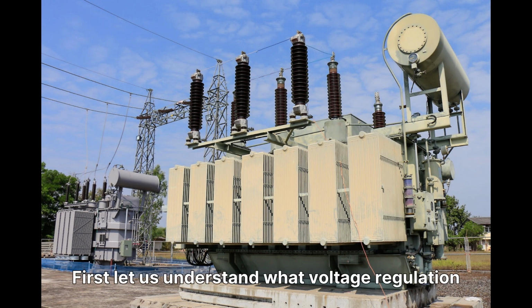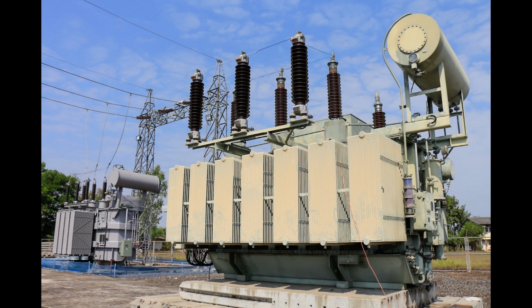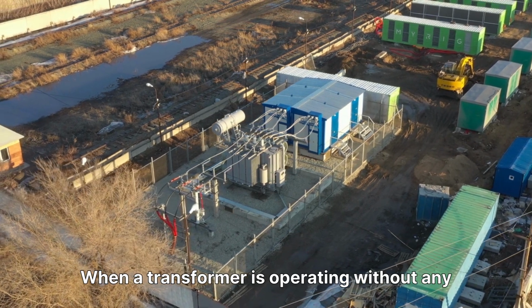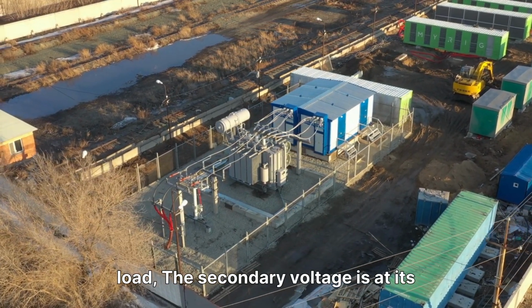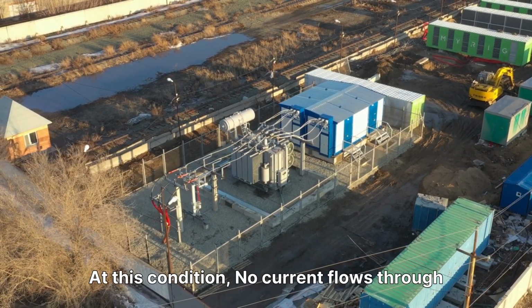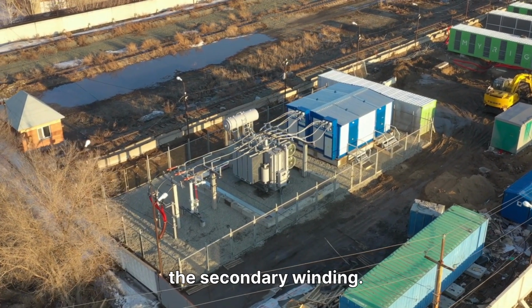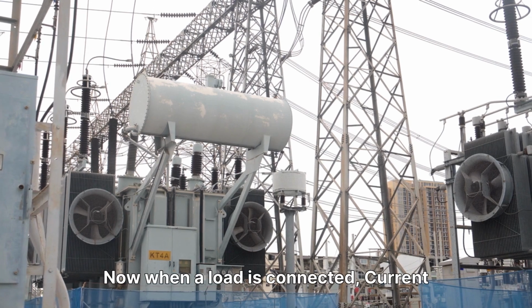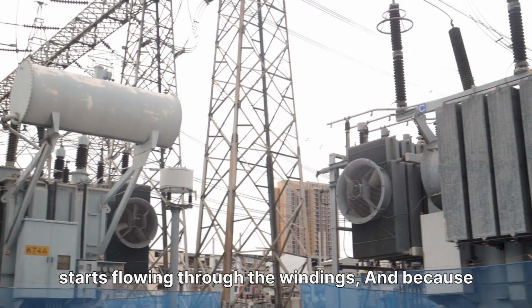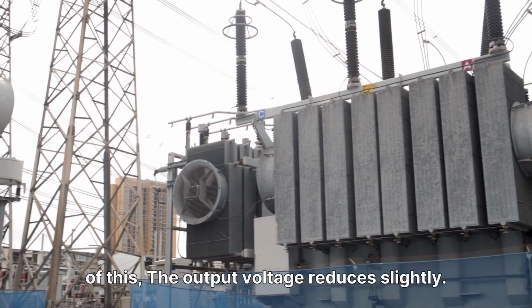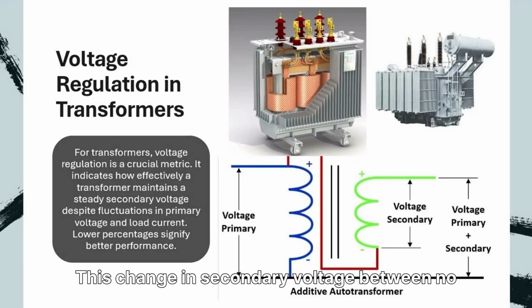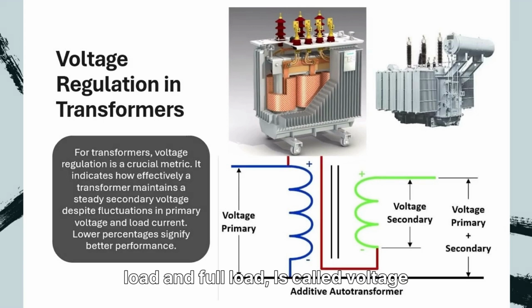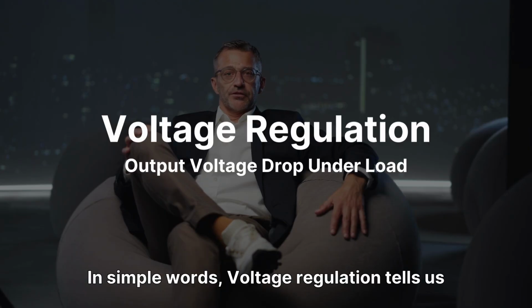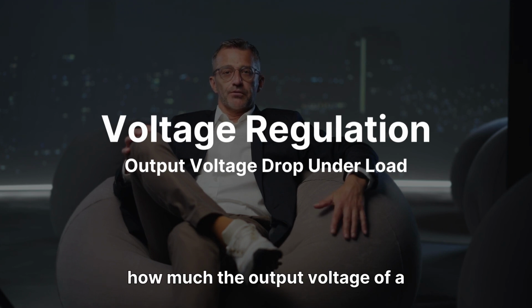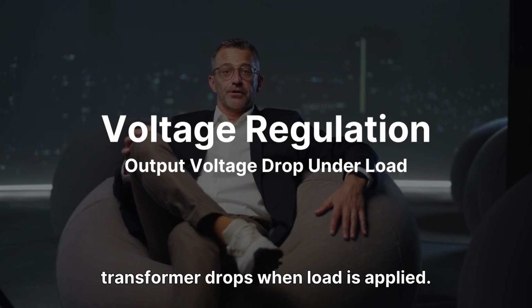First, let us understand what voltage regulation actually means. When a transformer is operating without any load, the secondary voltage is at its maximum value. At this condition, no current flows through the secondary winding. Now when a load is connected, current starts flowing through the windings, and because of this, the output voltage reduces slightly. This change in secondary voltage between no load and full load is called voltage regulation. In simple words, voltage regulation tells us how much the output voltage of a transformer drops when load is applied.